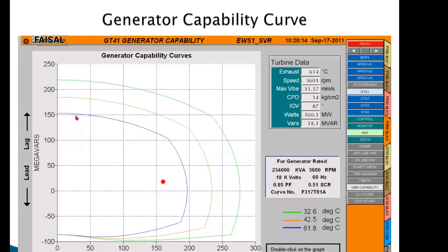One more thing you can see in this capability curve is the power factor. The minimum power factor will be 0.85. Ideally it should be 1, cos φ equals 1, so the ideal power factor for the generator should be 1, but the allowable minimum power factor is 0.85.